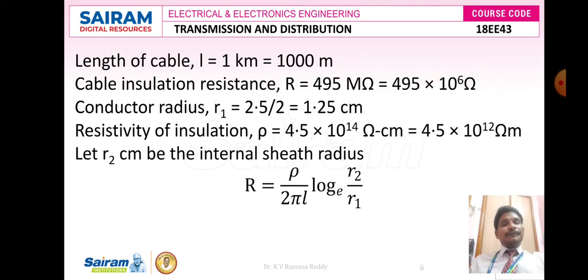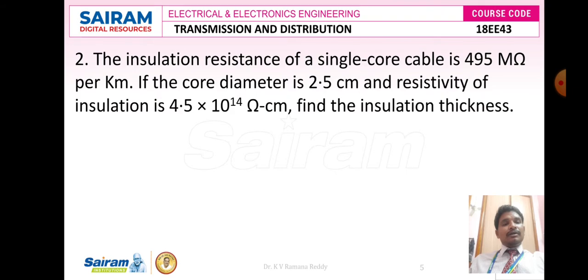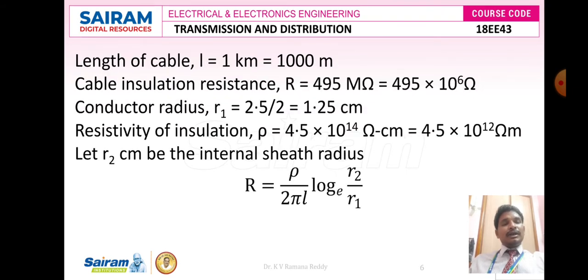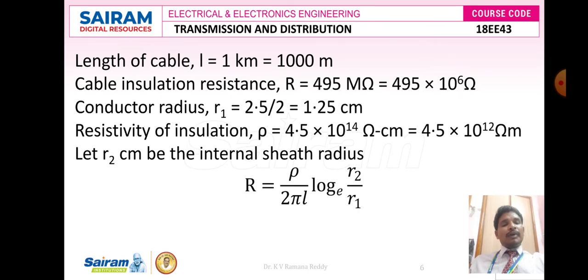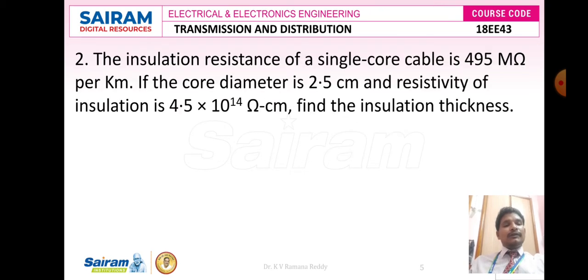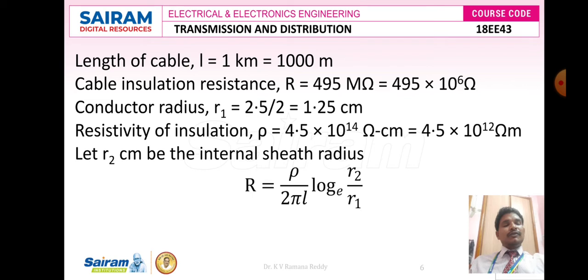From the given data: length l = 1 kilometer = 1000 meters. Cable insulation resistance R = 495 mega ohms = 495 × 10^6 ohms. Core diameter is 2.5 centimeter, so radius r1 = 2.5/2 = 1.25 centimeter. Resistivity ρ = 4.5 × 10^14 ohm-centimeter = 4.5 × 10^12 ohm-meter after conversion.